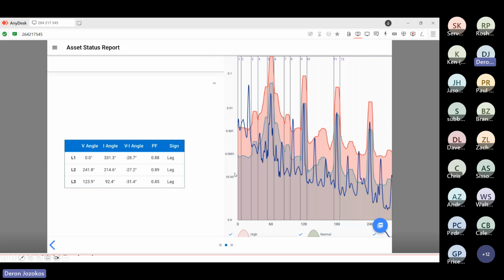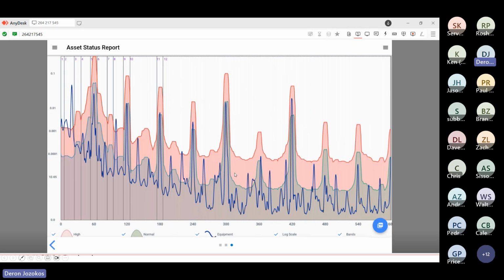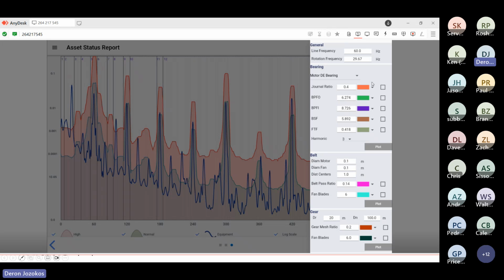So the last part of it is the actual spectrum. Now here we can do some advanced analysis right in the box. We can also open up the menu and plot out the different fault frequency bearings, and maybe the bar graph said we had a bad bearing here. You can plot out the inner race, outer race, and again, very similar to vibration analysis.